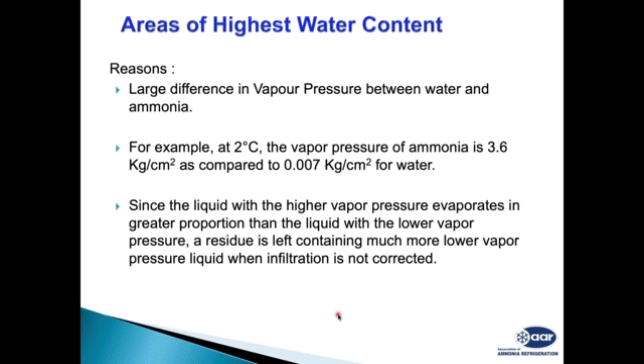Why does it go into the low side? Ammonia and water have a large vapor pressure difference. For example, at 2 degrees centigrade, the vapor pressure of ammonia is 3.6 kg per centimeter square, whereas the water vapor pressure is 0.007 kg per centimeter square. So when your plant is running and your suction pressure is 3.6, the ammonia will evaporate and the gas will go through the system, but water will remain at the bottom of the system. This water will continuously keep accumulating on the low side.